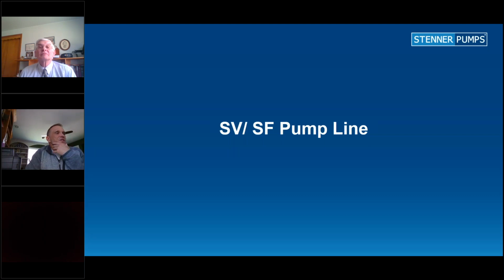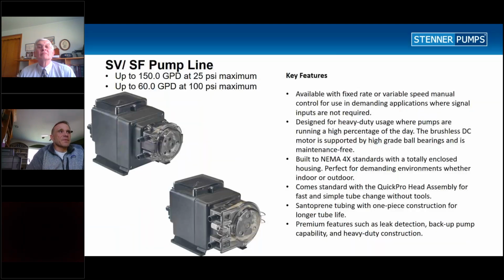One pump I wanted to mention that's new is our SV/SF pump. It's Stenner. In some cases, what we find is that with the classic pump, because it's a brushed motor design, sometimes the brushes will wear out, and the rotor or the coil will rust when it's exposed to chlorine and acid.